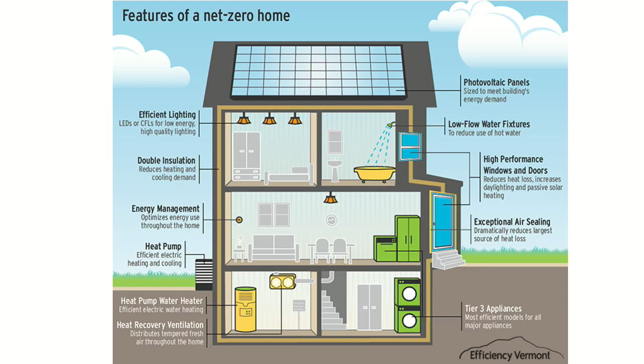So there's a few different types of heat pumps that we work with. Geothermal heat pumps are water-to-air heat pumps, so the water is the source that comes from the ground - we're using water often as a transfer fluid, and then it's distributed through the air, which is a refrigerant heat exchanger. Water-to-water means the source water comes in, and then we're also heating or cooling water out to the space, the load side.